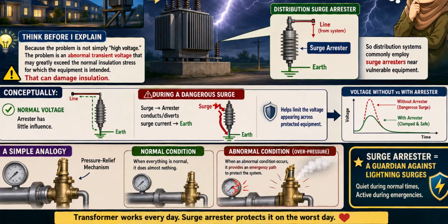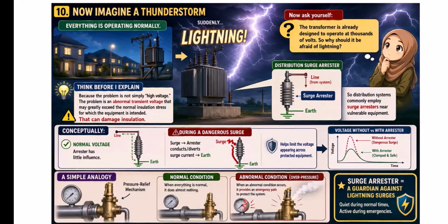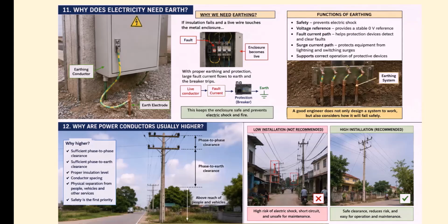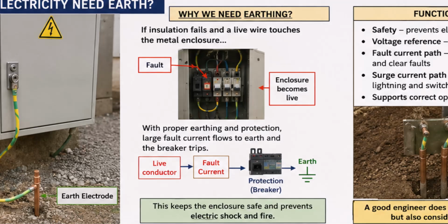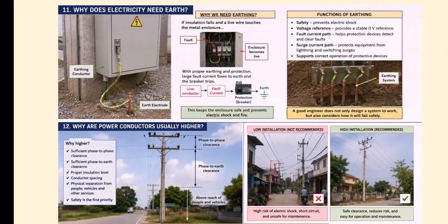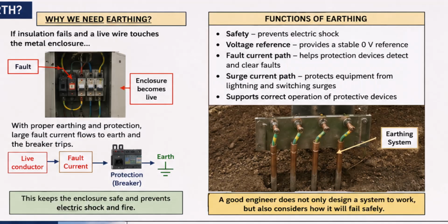A simple analogy is a pressure relief mechanism. When everything is normal, it does almost nothing. When an abnormal condition occurs, it provides an emergency path. Why does electricity need earth? That raises another important question. Pause and think. Why do we need earthing? Are we simply throwing useful electricity into the soil? No. Under normal operating conditions, the purpose is not to waste useful power into the ground. Grounding or earthing can serve several important functions depending on the system, including safety, voltage reference, fault current paths, surge current paths, and supporting correct protective device operation.